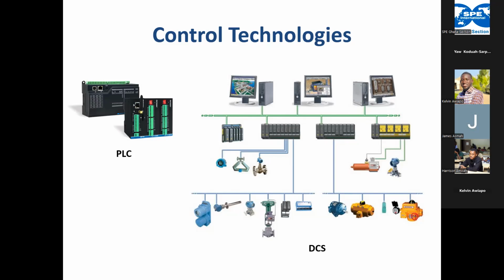and it can be reprogrammed anytime. And then we have the DCS that has multiple controllers which have been distributed in the plant. Each one is doing a specific function, but they are communicating together. And then you have the operator station that can monitor, and you can put any control action from there.